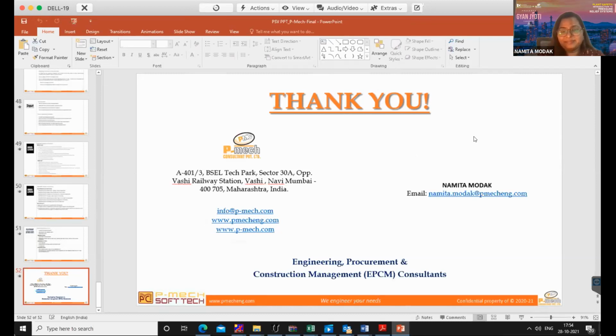My name is Lakshmi. I work for Archi Controls. I just want to know, you said for conventional PSVs, you offer them where the back pressure is like 10% of the set pressure, and where the back pressure is 50 to 70% of the set pressure, we have to go for the pilot operated ones. So what happens between 10 and 40 or 50%? There again, balanced bellows type, balanced. Okay, 30 to 50%. Yeah. Okay, fine. Thanks.